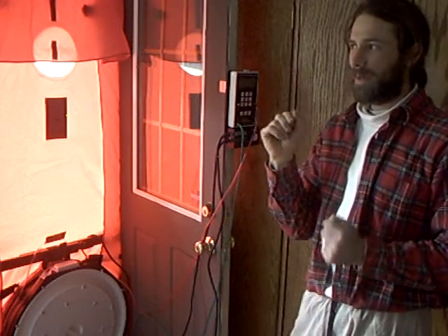And then what I do, depending upon the height of the house, its shielding, is I take the CFM 50 number, which is our depressurization number, and using some calculations, I determine how you compare to energy efficiency guidelines. What is the airflow under natural conditions through the house? And then, we're shooting for 0.35 air changes per hour as a building tightness limit that we try to reach. At that limit, you're not wasting heat through exhausting it out air breaches, and you're also maintaining indoor air quality.